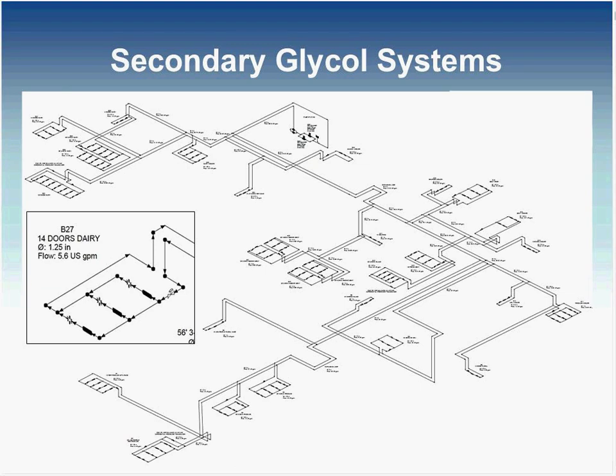It's something similar to a refrigeration system in that you're piping something from the back room all the way out to the different fixtures on the sales floor. The big difference is it's not refrigerant. It's simply propylene glycol, which comes out as a liquid and goes back into the back room as a liquid.